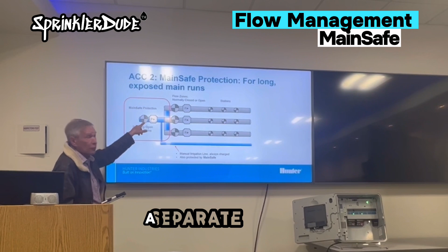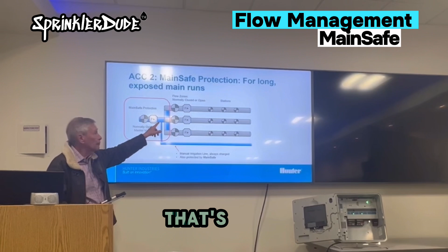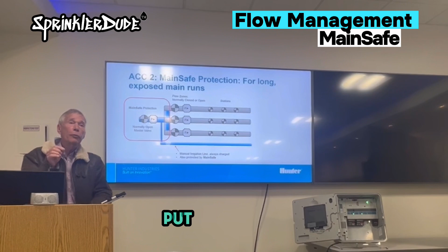MainSafe is a separate level of flow protection just for that giant water source. If this pipe breaks - it might be a 400 millimeter pipe, which is a whole bunch of inches - that's going to cause a disaster really quick. So what you do is set a number: I don't ever want to see more than X amount of flow running through this pipe.